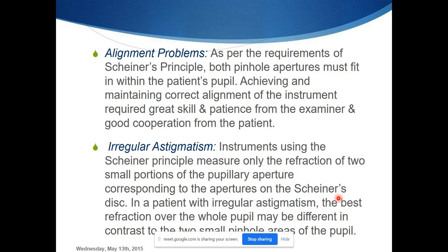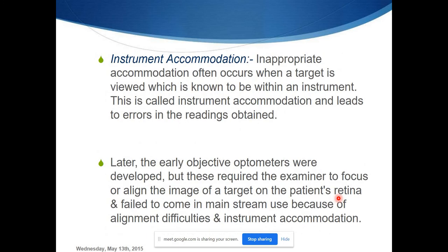Then comes instrument accommodation — however much we try to induce relaxation for distance, the instrument is still physically close to the patient, so the patient develops instrument accommodation. To overcome this, the first step is to fog the eye to relax accommodation before the instrument measures the refractive error. Instrument accommodation played a major role in producing inappropriate results.